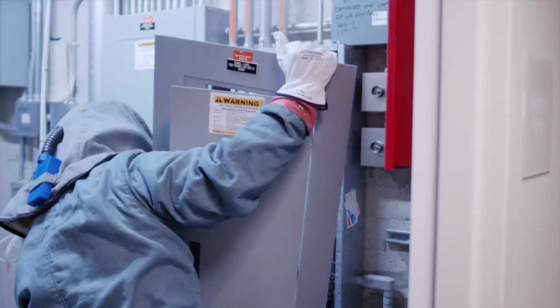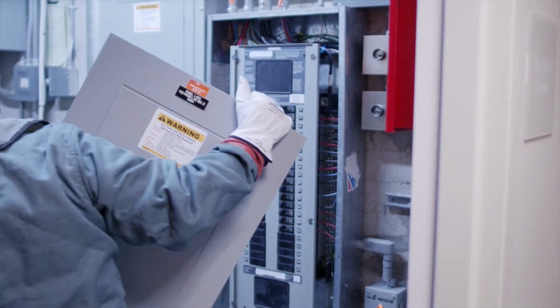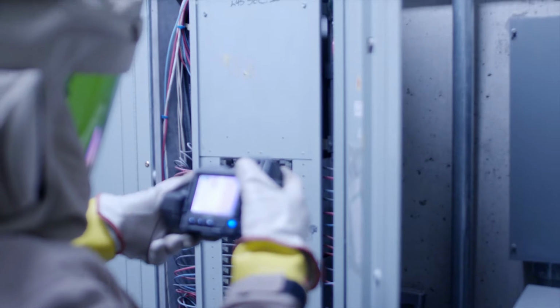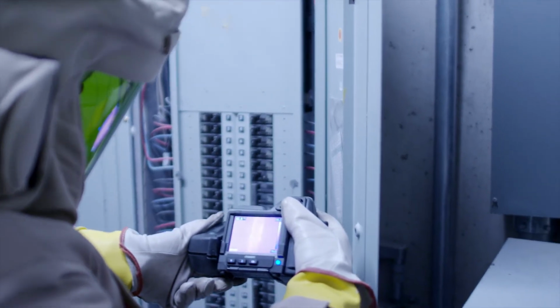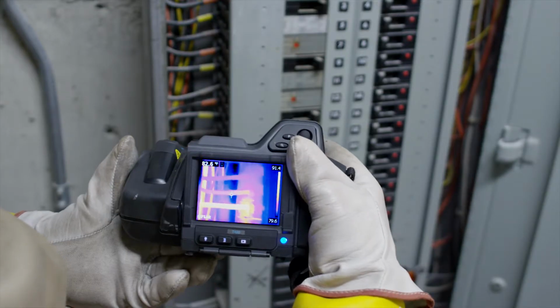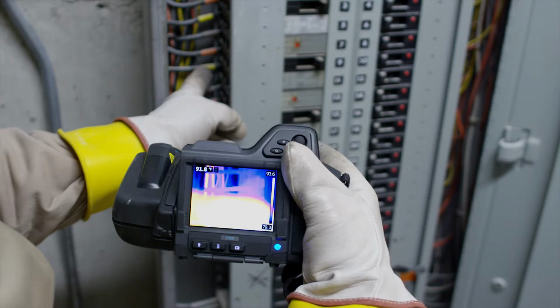There are certain things you can do without shutting your equipment down. The best thing is to do an inspection on the gear without getting inside and moving things around. The next best thing is an infrared scan, looking for hot spots. You just have to make sure you have the proper PPE to open the gear, and you should be able to identify hotspots with bad connections.